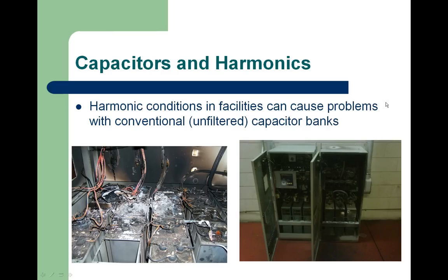We also have some pictures of some failed capacitors. Capacitor banks sometimes carry a negative note to them where people have had some problems, and these sometimes, or a lot of times actually, are due to harmonic currents. And again, we'll get into that a little later. So these are a couple of, I'd say, catastrophic failures. The one on the right here, actually it's the section on the right side of this automatic bank that had actually failed, and there was a fire involved in that.